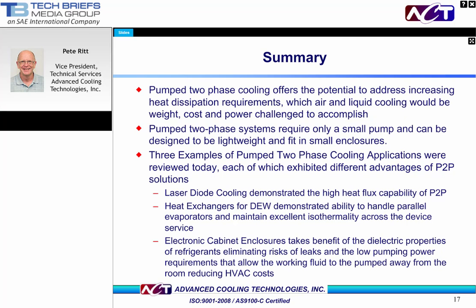In the webinar today, we have reviewed pump 2-phase cooling, its advantages, operation, challenges, and some new technology being developed to address these challenges. Pump 2-phase cooling offers the potential to address increasing heat dissipation requirements up to 1,000 watts per centimeter squared by some estimates, which air and pump liquid cooling would be weight and power challenged to accomplish. Pump 2-phase systems require only a small pump and can be designed to be compact and lightweight.